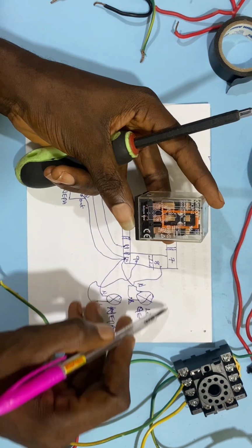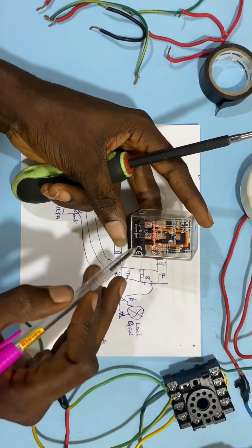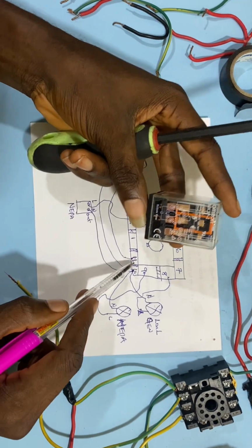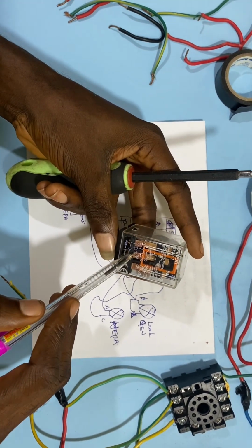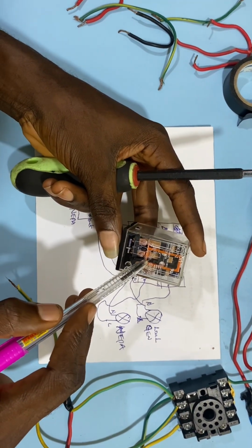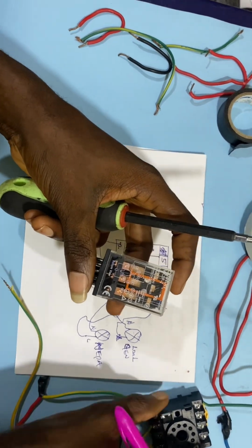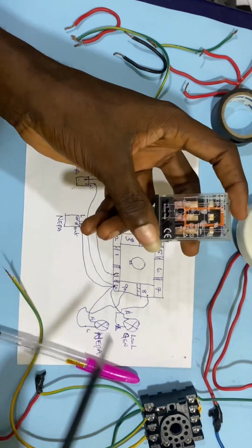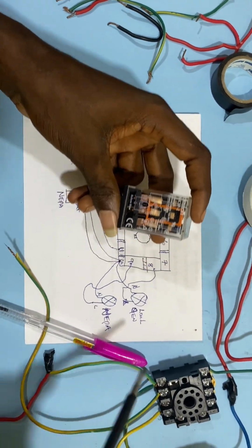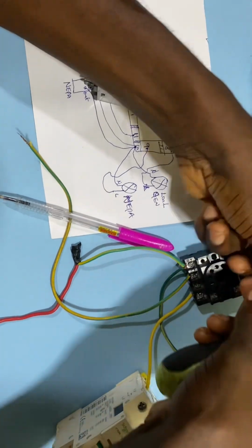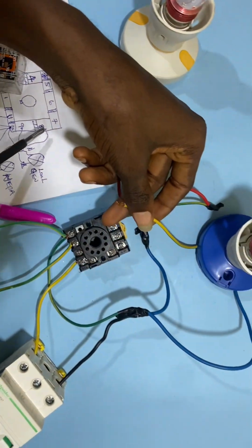And the load of pin 8 will now turn normally open. So pin 8 was closed before, so it's going to turn normally open as soon as the coil contact is powered. But initially, you see the gen was just entering from pin number 11 and is powering through pin 8. Now we are done with all the wiring, so we need to connect the load of our generator to pin 8. So this is the load live of generator, and we are going to connect it to pin 8.